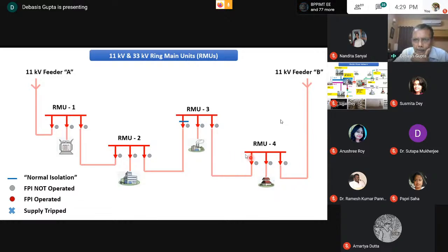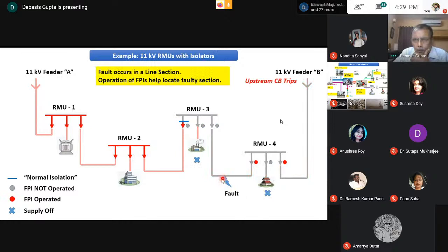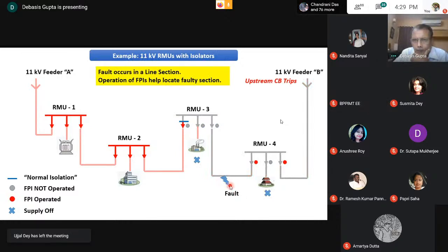Now let's assume there is a fault in this section. So what happens? Once this fault has occurred - in our case in CESC we don't have breakers, so naturally the upstream breaker here has to trip. But if you go to Delhi or Bombay, the breaker here would have tripped. Coming back to Calcutta, this breaker has tripped here. So this entire line is dead up to here.